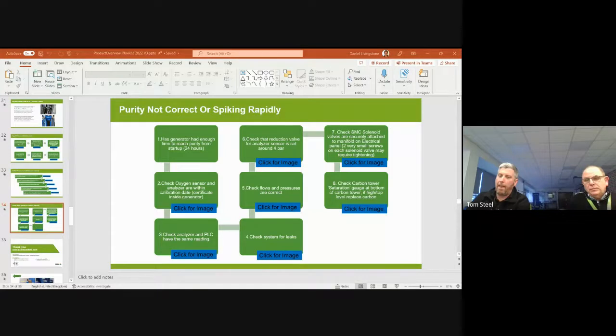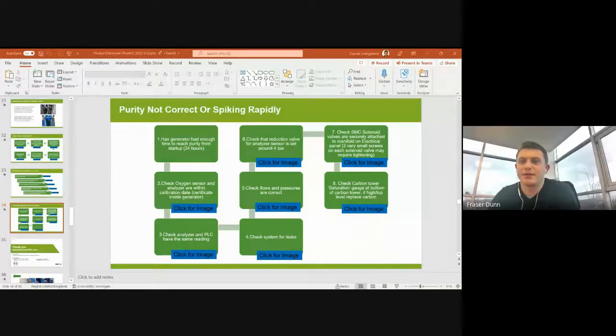Thanks, Tom. Fraser, did you want to just add on to that? Yeah, just a very little bit. It's a hard one to put a definitive answer on. A lot of it depends on the application and how the instrument's being used. Typically, what you would find with O2 PSA plants is they are designed to produce what's called oxygen 93, so it's between 90 to 96%. I know certainly in the UK there's another standard, a medical standard, where our health service requires 94% or above. So generally speaking, it's very hard, and it comes back down to the specific application of how the instrument's being used.